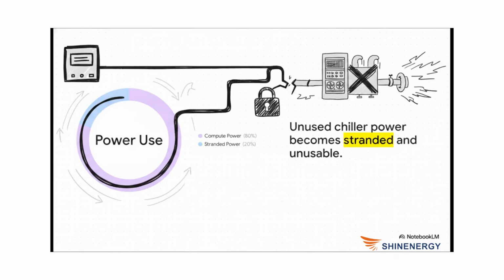And that is the exact speed required to smooth out the incredibly volatile power demands of a modern AI learning cluster. And all of this speed and software control goes straight to the bottom line because it solves a massive industry headache known as stranded power. In a traditional setup, you have to dedicate a physical hardwired feeder to a cooling chiller. Let's say that chiller accounts for roughly 20% of your total facility power budget. Because it's hardwired, even when the weather is cool and that chiller isn't running at full capacity, that 20% power is essentially trapped. It's stranded.